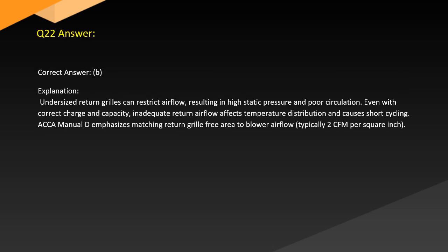Answer. Correct answer, B. Explanation. Undersized return grilles can restrict airflow, resulting in high static pressure and poor circulation. Even with correct charge and capacity, inadequate return airflow affects temperature distribution and causes short cycling. ACCA Manual D emphasizes matching return grille free area to blower airflow, typically 2 CFM per square inch.